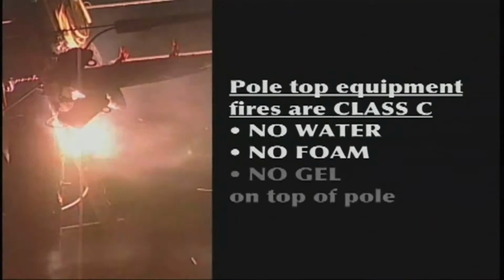Your first task on a pole fire is to identify the problem, because your response depends on what is on fire and where the fire is on the pole. Most fires at the top of the pole are pole-top equipment fires, involving a transformer, capacitor, insulator, switch, automatic switch, or other apparatus attached to the pole. Consider these energized electrical fires as Class C. Do not spray water, foam, or gel onto any pole-top equipment or fires at the top of a pole. Call Edison and wait for a qualified utility worker to arrive.